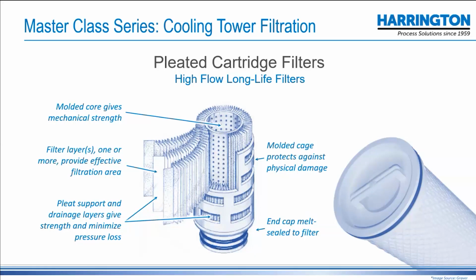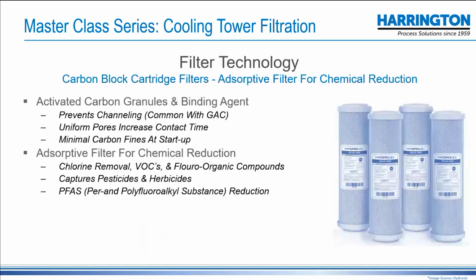If it's much larger, and a lot of times we'll see 50 micron process cooling water high flows, I'd recommend a screen instead, simply because it is self-cleaning. You don't have a consumables cost. But pleated is basically taking a material and then compressing it, like the hem of a skirt, so that you get more surface area, and therefore you've got a prolonged life. Then there's the carbon block, for removing chemicals like chlorine or VOCs or organics. Compared to a media filter, a carbon block has the advantage.